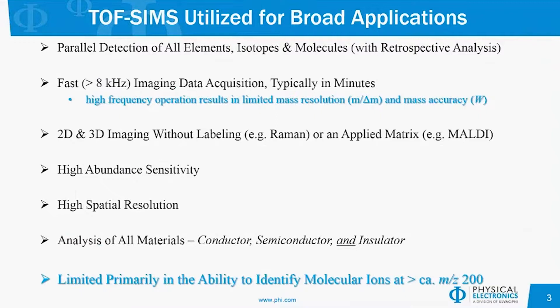TOF-SIMS is a fast imaging technique. Typically you can collect images of the surface in a matter of minutes. Two-dimensional as well as three-dimensional imaging is possible without labeling, as would be done in Raman, or without an applied matrix, as is necessary in MALDI mass spectrometry. SIMS is very sensitive and we achieve quite high spatial resolution — down below 100 nanometer spatial resolution is possible. TOF-SIMS can look at any material, whether it's an insulator, conductor, or semiconductor.